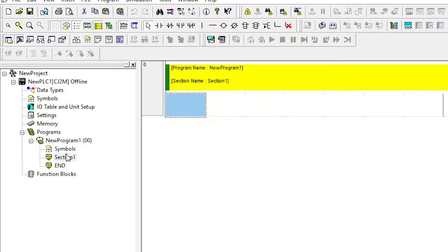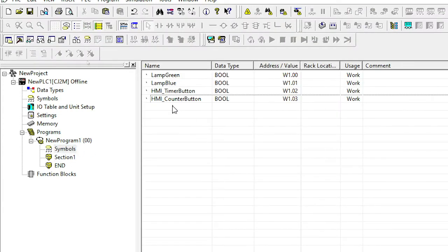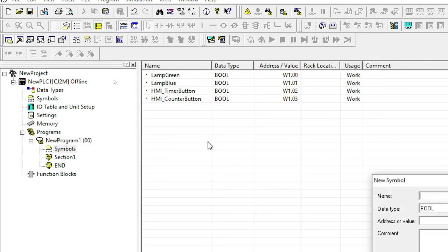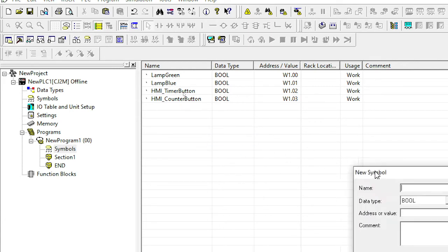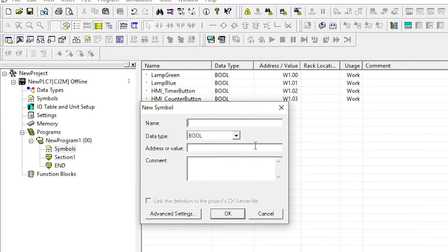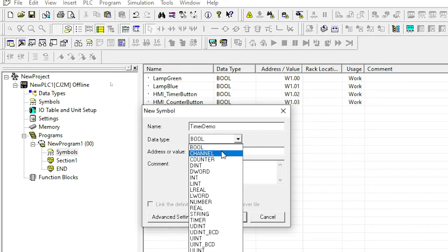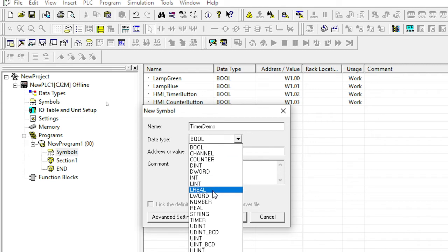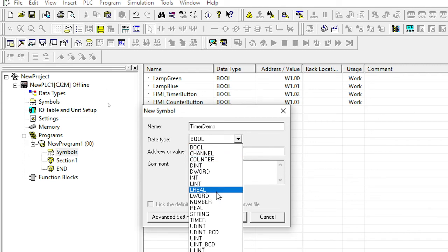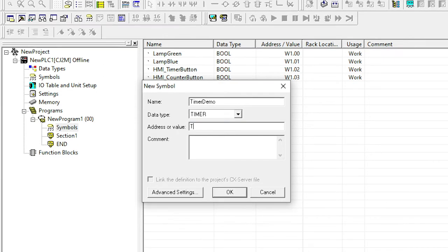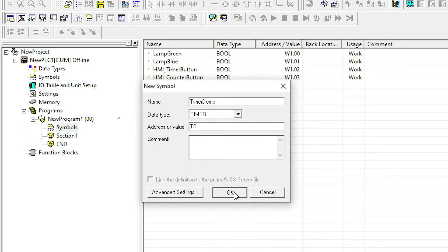And the first thing I need to do is I'm going to add a timer. So let me go to the symbols again, insert symbol. And I'm going to call it timer demo. One of the biggest mistakes students make is they forget to change the data type from Boolean to timer. So if you look down here, I have a counter and I have a timer. So I'm going to select timer. And I'm going to give that T and I'm just going to put it in T0.